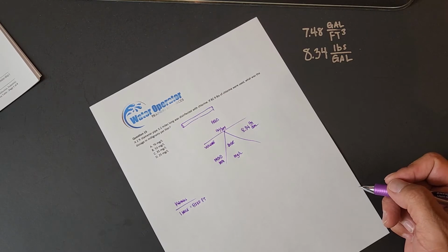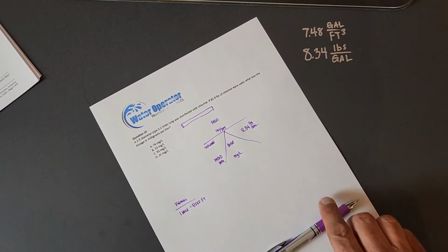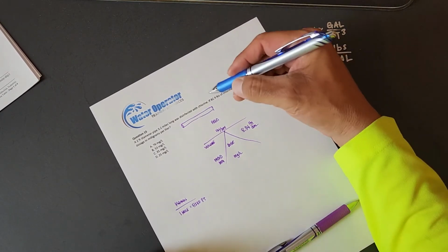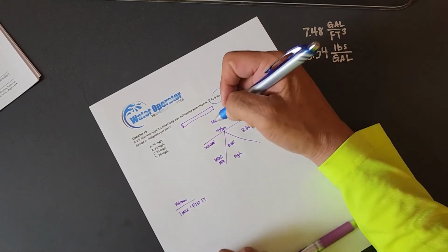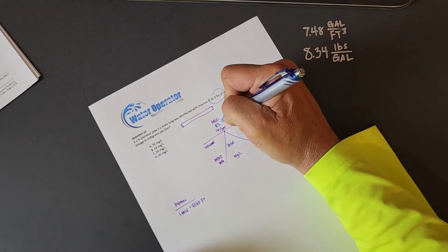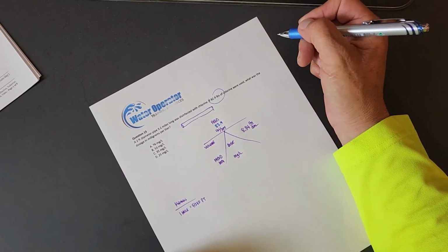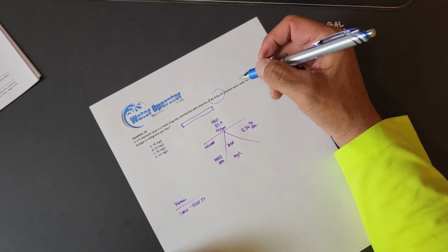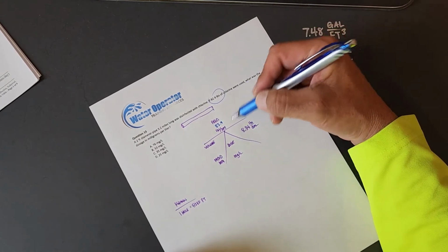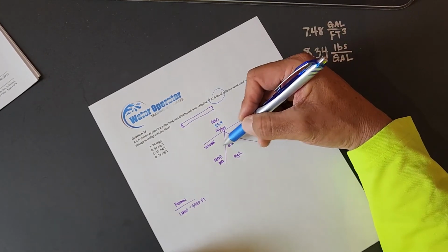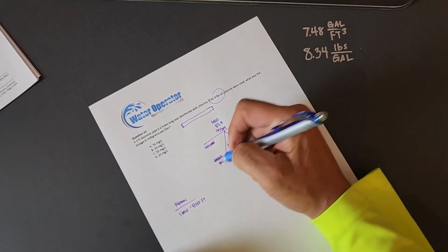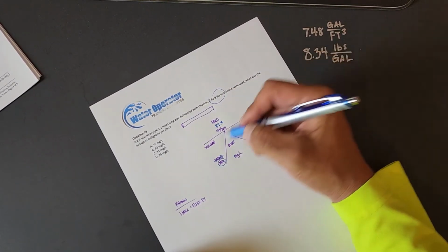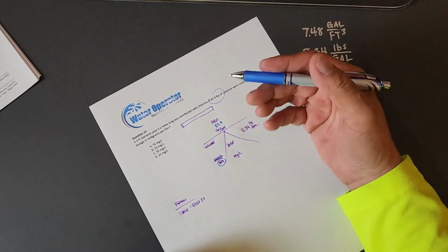So let's fill in some information here. We have 82.9 pounds of chlorine. We'll go ahead and write that right there. We don't have the dose, that is what we're looking for. The volume in million gallons, and let's just go ahead and put a line through there. The volume in million gallons is what we need to calculate.